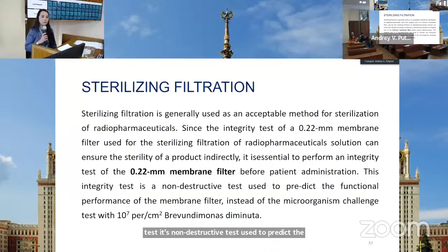But for each type of filter, when we use sterilizing filtration, we should do an integrity test. The integrity test is a non-destructive test used to predict the functional performance of the membrane filters. For this test, we can use special equipment that can be included inside the hot cells in the grade A area. It's bubble point test equipment. And for each batch, we should perform this test before and after dispensing.